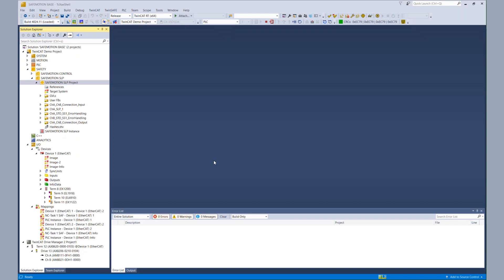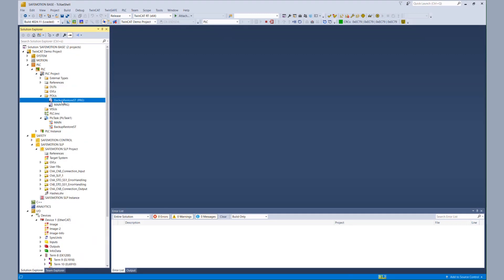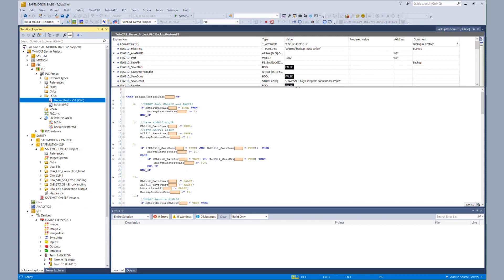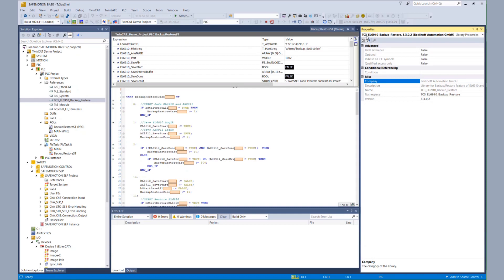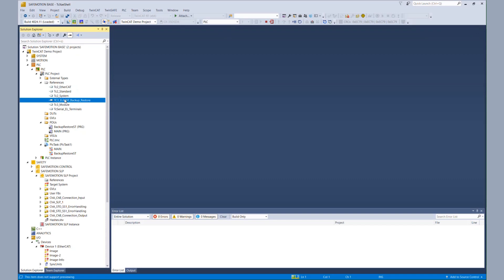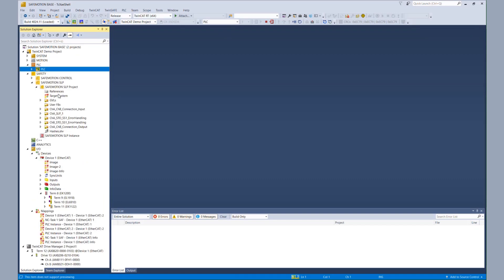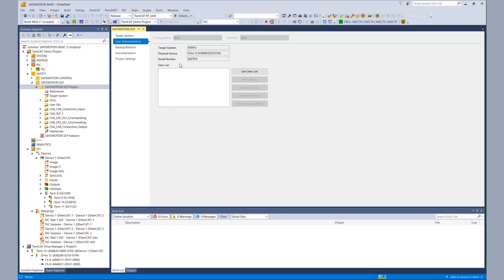At the start of the tutorial, we have a TwinCAT 3 solution where we also have a standard PLC, and there we created a program for the backup and restore mode with a little state machine. We have already imported our TwinCAT 3 EL6910 backup and restore library in version 3302. Before we show the usage of the library, we have to configure our safety project. In the first step, we also want to restore the user management, so we create a new user for the AX8000 via the target system configuration and user administration.